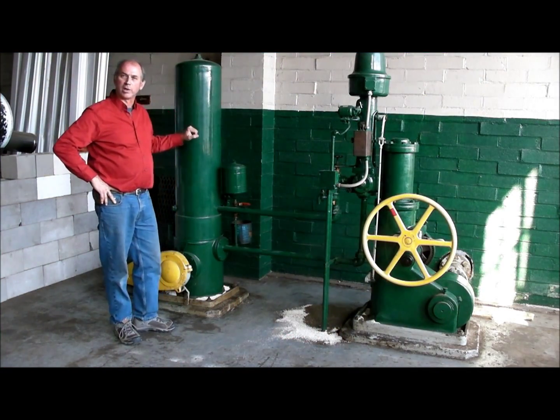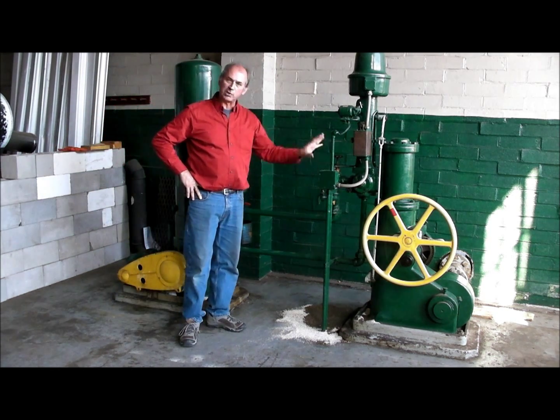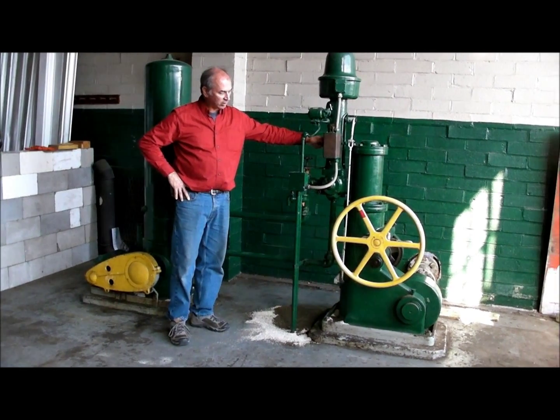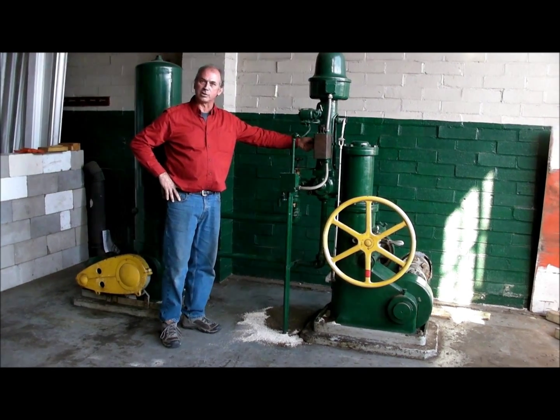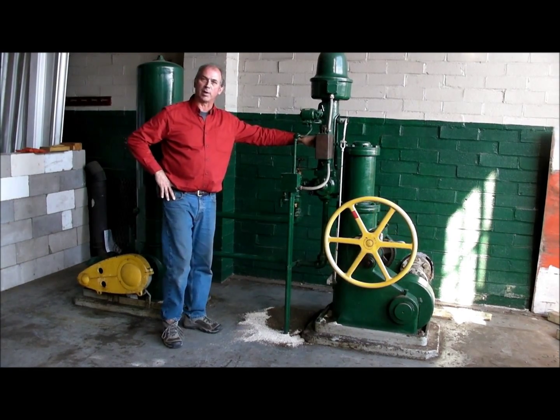This unit here is a Hayward governor built back in the early 1900s. What this unit does is open and close the gates on the turbine. When you have less water, you have to close the gates down. As you can see, the hand wheel turns and closes against it, reducing water consumption and power. Right now, we just had a lot of rain, so we're running at 100% capacity.